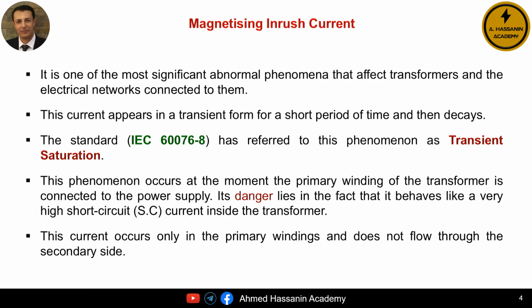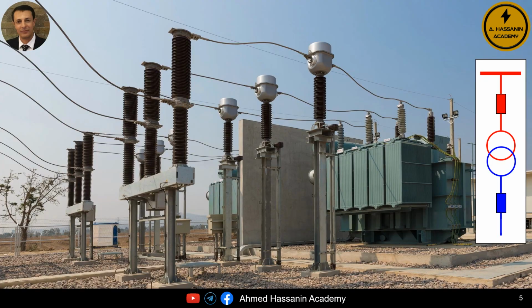The second point is that the magnetizing inrush current occurs at the moment the voltage is applied to the transformer or at the moment the primary windings are connected to the power supply. Naturally, this current appears as if a short circuit current has occurred inside the transformer. Now we want to understand how this phenomenon actually occurs in a clearer and more systematic way. As we can observe, there is a power transformer located in a substation, and this transformer is in service. That is, it is energized. In other words, the primary side of this transformer is connected to the power supply or the main bus bar, and the secondary side of this transformer feeds various loads.